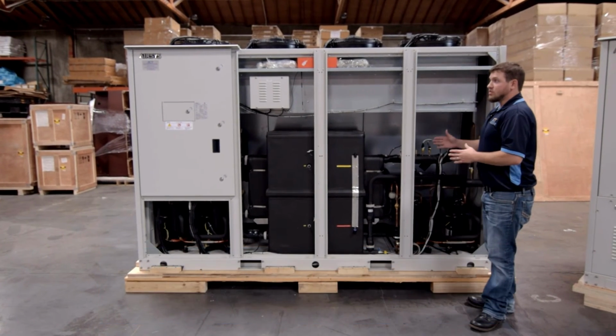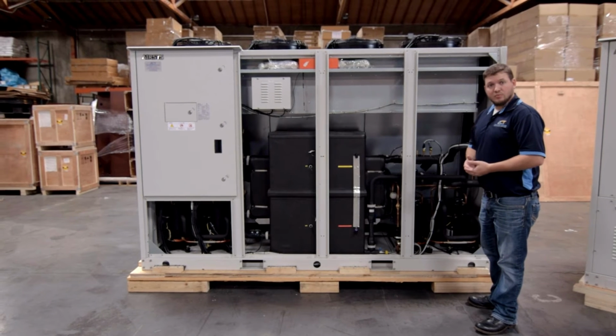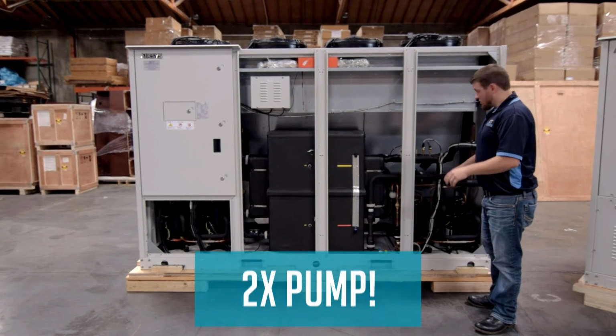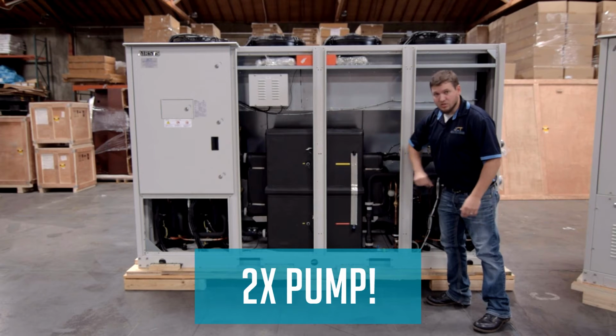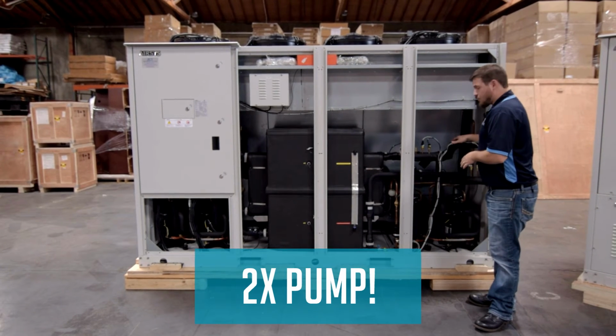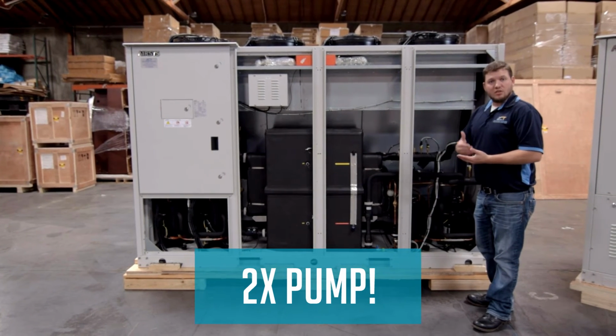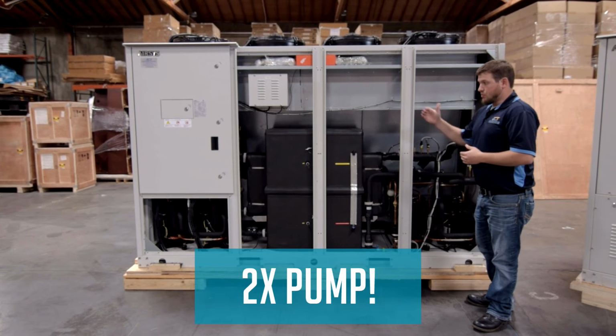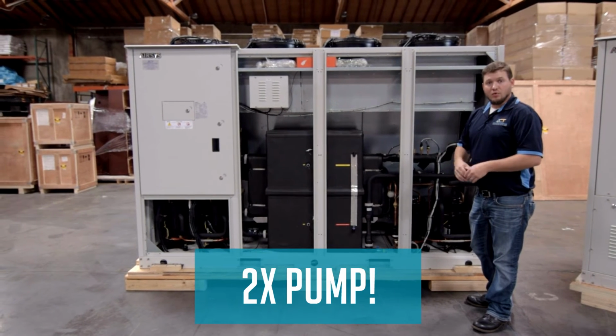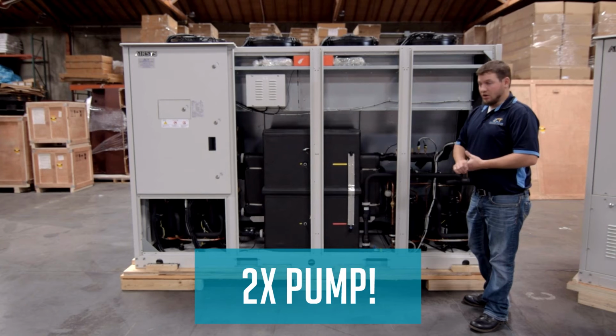On top of this, Airsys uses high quality Grundfos pumps. There are two in the system, one behind each refrigeration system. If for some reason there is a failure of a pump, the other pump will turn on automatically, reducing the risk of ever having a failure resulting in downtime.